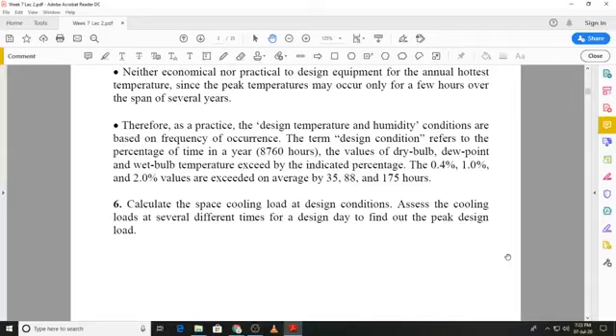For most of the year, or practically for the entire year, it's possible that your plant will actually be running at a much lower load, and when it runs at a very low load compared to the design load, it's also operating at a very low efficiency, so you will be losing money. So instead of just focusing on one particular maximum temperature, the practice is to select the outdoor design temperature based on what is known as the frequency of occurrence.